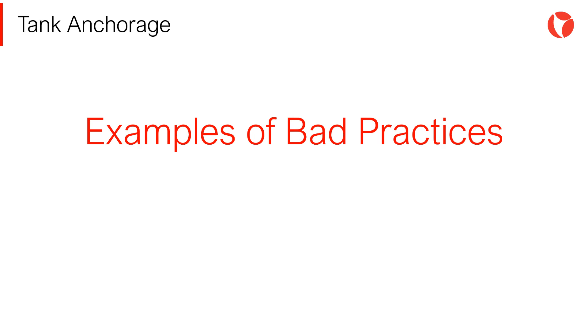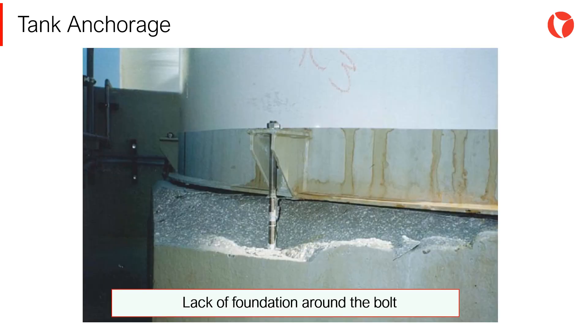As has been seen so far, anchor bolts are a fundamental part of this type of equipment, basically to counteract the seismic effects and the actions of the wind. A good design with a bad execution is useless. When a tank requires anchor bolts, the design of the foundation that will bear these elements is critical. The figure shows a badly designed foundation where concrete is missing to contain the loads transmitted by the anchors.